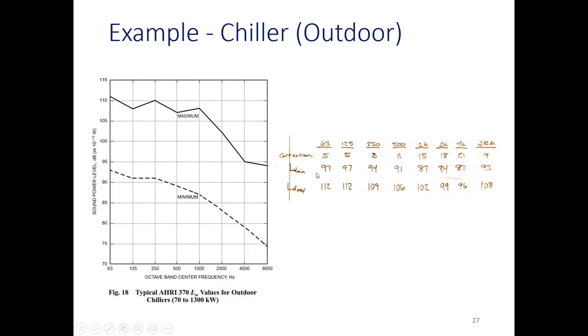Let's compare. On the minimum, we have 97, 97, 94, then 91, then 87. So at this point, we were a little bit high on the low end. One thing: this method is from Hoover and Keith, and I've noticed Hoover and Keith is conservative. I think they probably do that as a liability thing for themselves, and for you too, just to make sure you don't underestimate how noisy something's going to be. But they're a little over, only like 4 decibels.